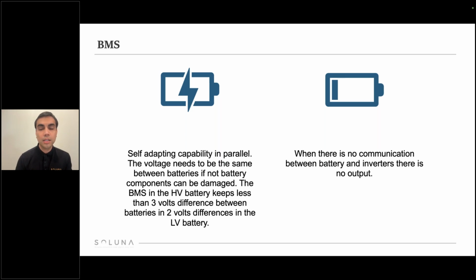The BMS in our batteries allows for self-adapting capability in parallel, which allows the voltage to always be in balance. So the voltage needs to be the same on all batteries for better performance and to maximize the lifespan of the battery. But if the voltage is not balanced, it can damage the components within the batteries. So the BMS in our high voltage battery keeps less than 3 volts difference between batteries, and in the low voltage it keeps less than 2 volts difference.